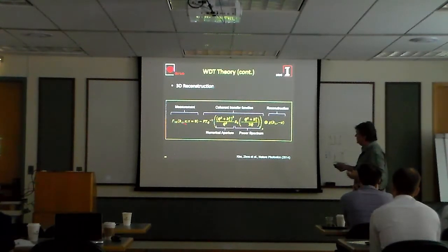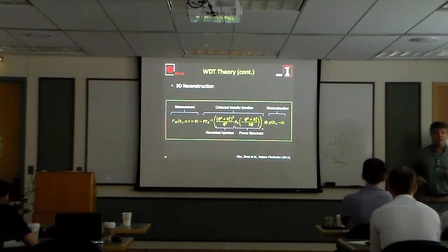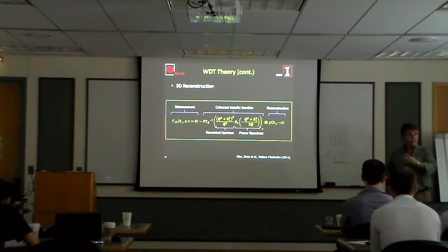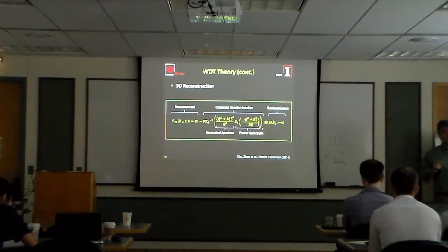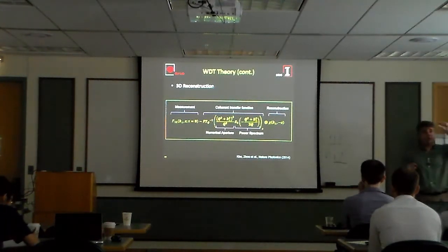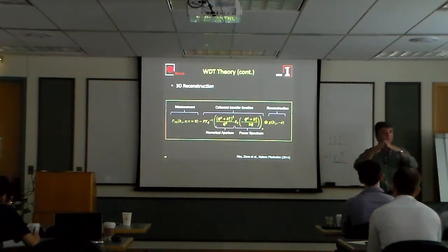This is the measurement. Let's say this is the correlation function. This is the phase image, if you want. And basically, in the z direction, you get your structure convolved with this mess, meaning that you don't get perfect resolution in z, you get blurring in z, as we might expect. The whole struggle was, what is that blurring? What is that function? And now we know what it is. We knew all along that there are two components to it. One is the coherence effect, the fact that white light has a very broad bandwidth, and the coherence length is only about 1.2 microns. But we also knew that the higher the numerical aperture, the better.